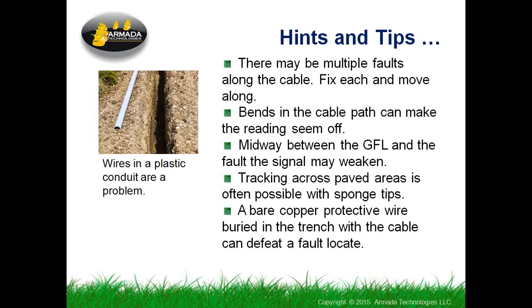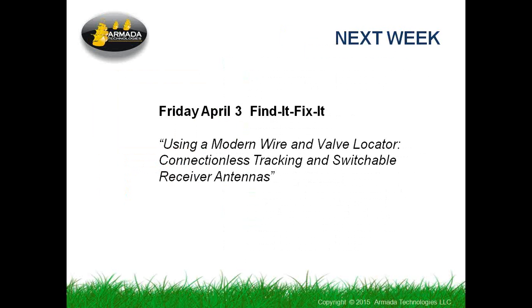I have heard some issues that have been raised recently. People with 2-wire irrigation systems that have lightning protection may have a buried, uninsulated copper wire next to the main cable. That will tend to mess up the whole ripple situation, because the copper wire will absorb the ripples. You may run into that if you're in a 2-wire system or a system that has lightning protection. You might watch out for that if you're getting very difficult readings. There's no handy way around that, I'm afraid, that I'm aware of.